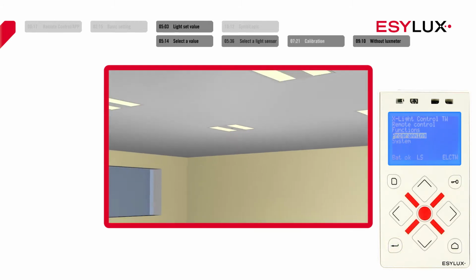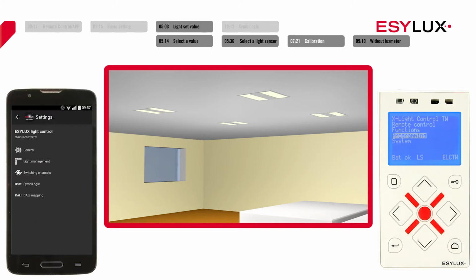If you use lights with additional light sensors, these sensors must be calibrated. Otherwise, the light sensor in the presence detector will be used, provided it is activated. A lux meter is required for calibration. If you do not have a lux meter to hand, you can also adjust the brightness manually. We will start with the more precise variant with a lux meter. If necessary, darken the room to prevent the calibration process from being disturbed by foreign light sources. The light sensors must be calibrated with 3 measurements at least once per lighting channel.